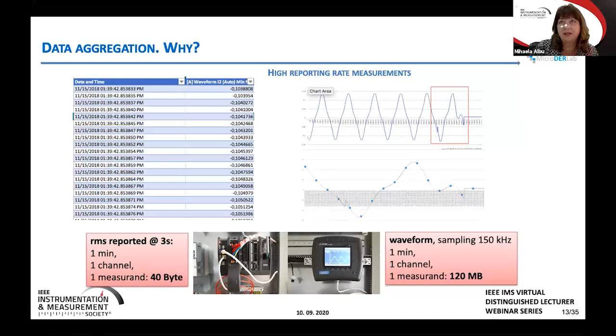Well, it's a very easy answer. If we consider a waveform point measurement sampled at 150 kilohertz, not an unusual sampling rate, used for instance by micro PMUs, for 1 minute, one channel, one quantity, one measurement, this results in 120 megabytes. While acquiring the RMS values and performing an aggregation over 3 seconds requires, for the same channel, only 40 bytes, assuming 2 bytes per data result.